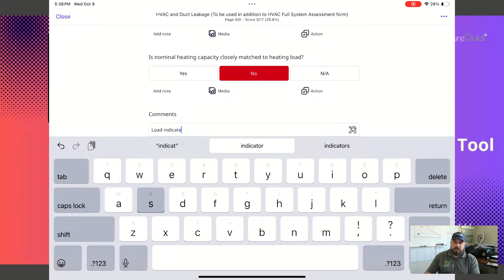This is where I answer a couple of questions: is the nominal heating and cooling capacity closely matched to the heating load? Whether it is or not helps me build recommendations down the road. I may not always tell somebody they need to immediately rip out an oversized HVAC system, but when it's time to replace it, I'll tell them we need to go back with a smaller system. Let's keep rolling here.